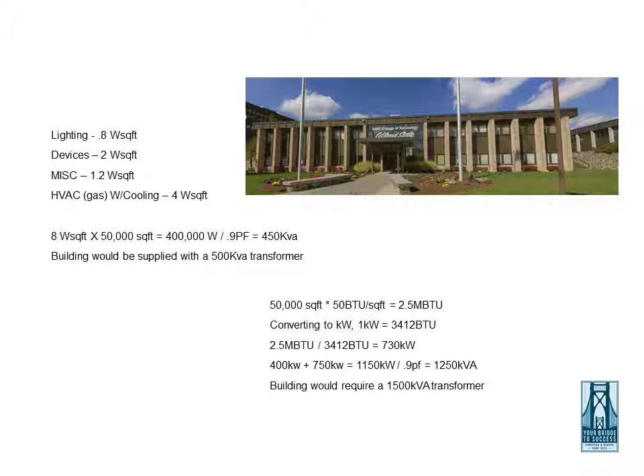For our typical 50,000 square foot building with the aforementioned loads, we would consider 400 kW total load with a potential power factor of 0.9. Our kVA would be around 450. Using round numbers, the building would be supplied with a 500 kVA transformer and service.